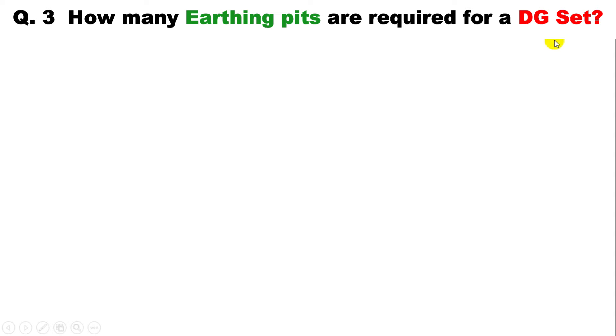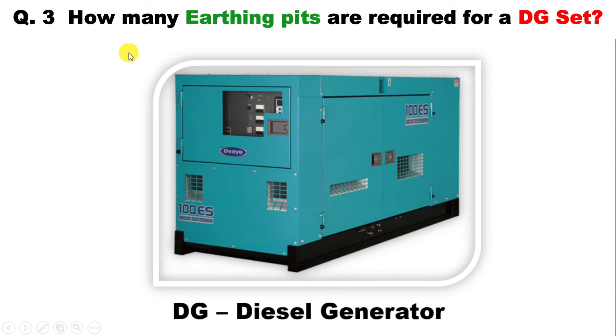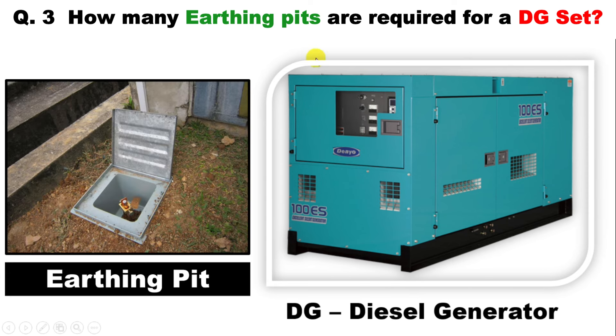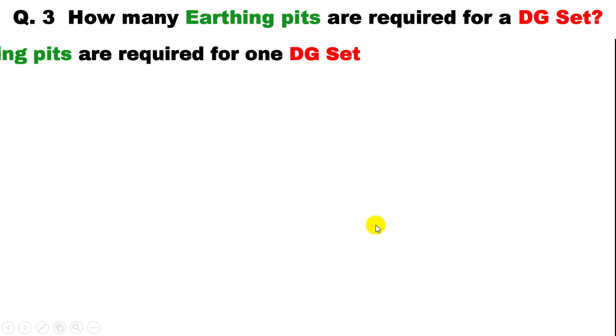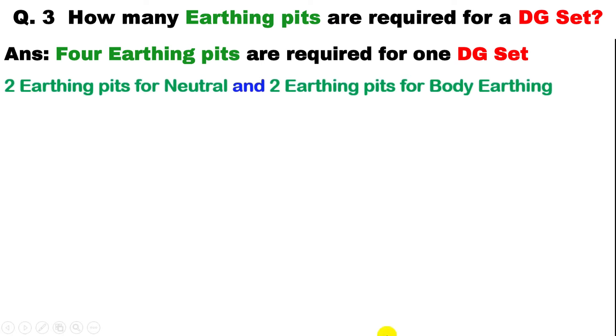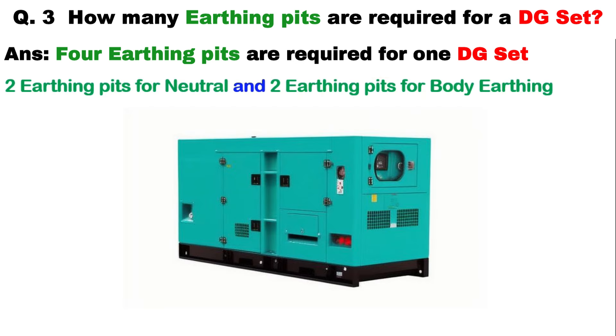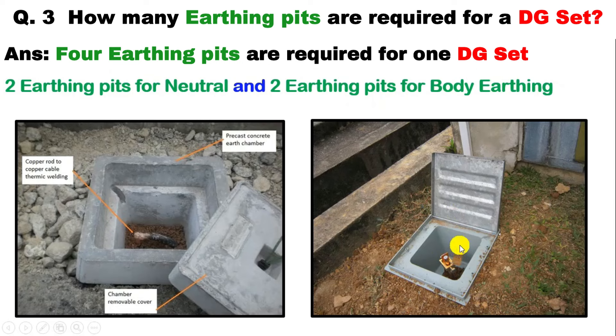The next question asks: for a DG set, how many earthing pits are required? DG set means diesel generator set — when electrical power supply is gone, we distribute power supply through the generator. The answer is: for a DG set, four earthing pits are required — two earthing pits for neutral and two earthing pits for body earthing. The neutral output must be connected to a neutral earthing pit.